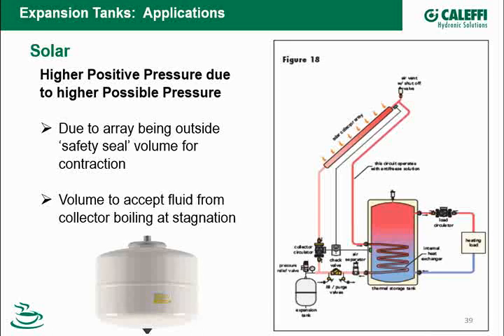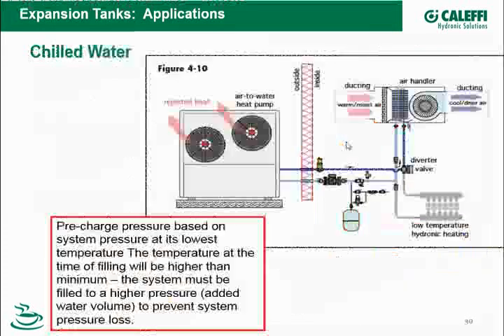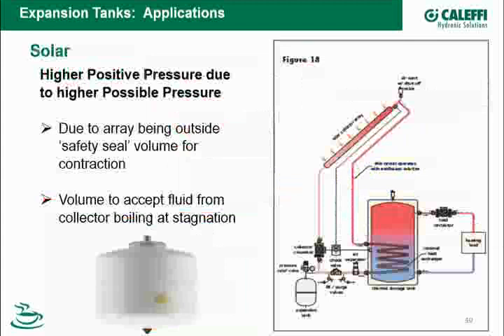Now, something else that comes up in various manufacturers' installation and setup manuals is something called a safety seal. The solar collector is outside the building envelope, so the water in the collector has the ability to contract as outside temperature drops. If I fill the system up on a 60-degree day, and during that night it drops down to 30 degrees, the water in that collector is going to contract. Most manufacturers looking for this safety seal will say to pre-charge the tank to the static pressure and then fill the system 2 to 3 psi higher. You'll have a little bit of water sitting on top of the diaphragm in that expansion tank that I can then let the system use to keep the pressure on the system when the fluid in the collector contracts.